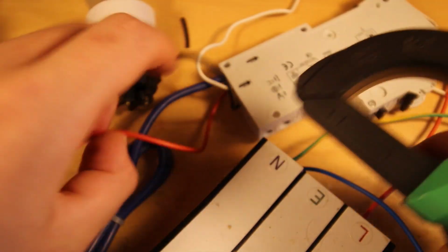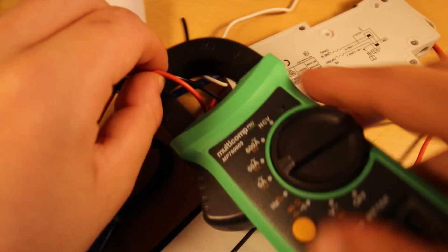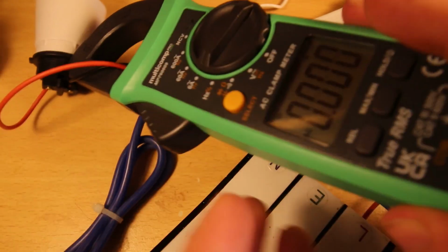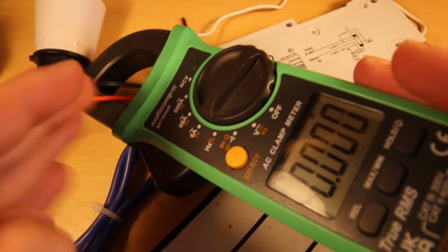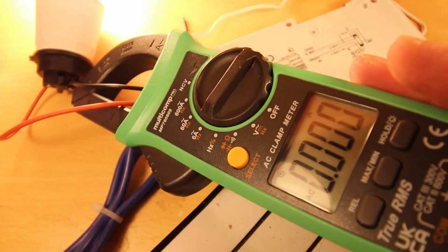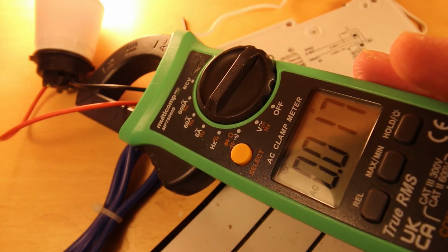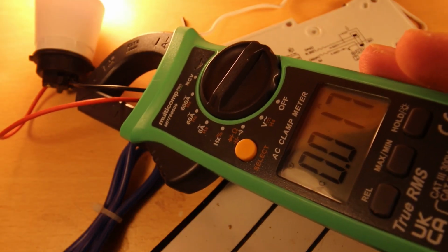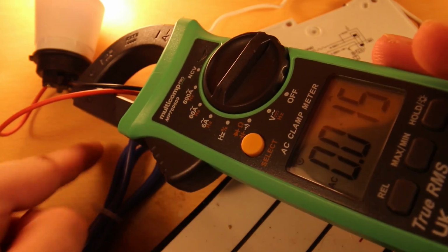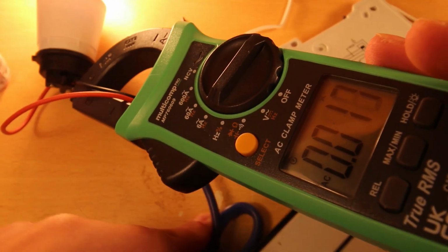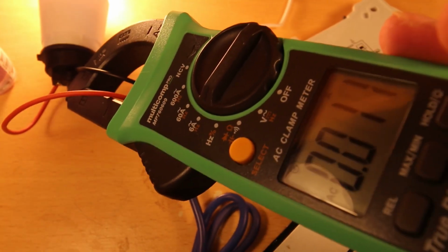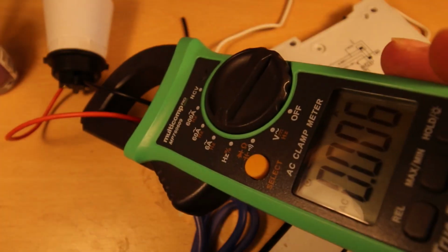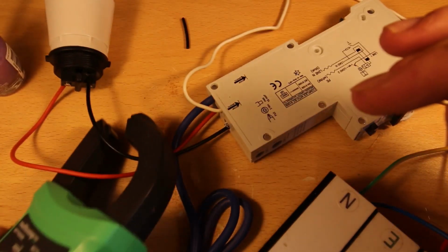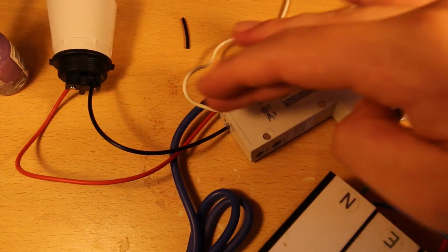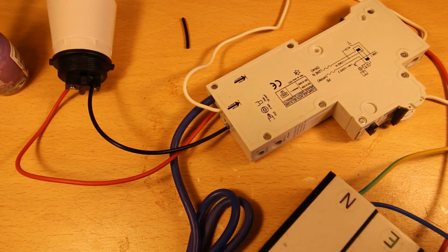If I then put both of these around, this is with the lamp connected, so the leakage it is measuring is 17 milliamps, which is obviously not true. That's because it's being interfered with by the neutral. If I move this, it probably will, yeah, it goes down. So the leakage is effectively 0. This meter gets confused if you have other current carrying conductors nearby.